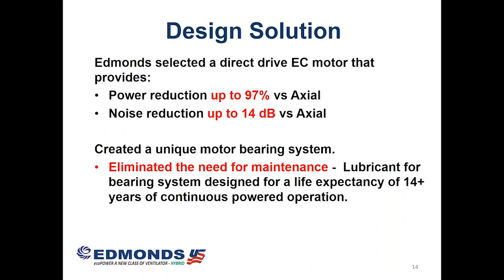Noise reduction was up to 14 decibels lower than equivalent standard axials. Moreover, the motor required no regular maintenance cycle and had a grease bearing life in non-stop mechanical operation of over 14 years. The slide I'm showing now was meant to provide a quick demonstration of the smoothness of the mechanical operation and the low noise output.